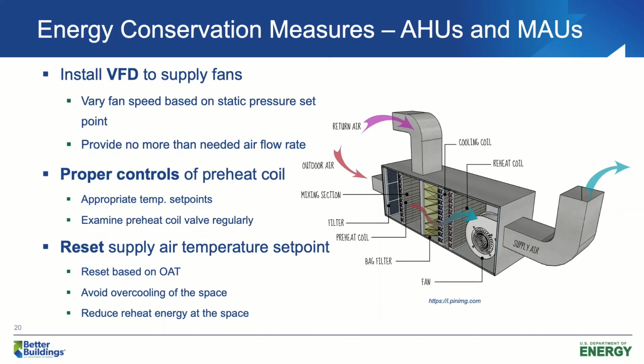Proper controls of the preheat coil. We would like to make sure that we have an appropriate temperature set point for preheat coils. Typically, we only want to warm the air up 3 to 5 degrees above freezing point. We do not want to warm the air up too much, otherwise we are adding heat to the airstream, adding more cooling load to the main chilled water coil. We recommend checking preheat coil control valves regularly and making sure that there are no leaks through the coils, because leaking hot water through preheat coils will add a lot of heat to the airstream.